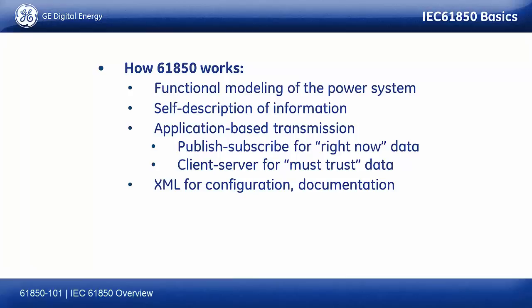What 61850 works on is functional modeling of the power system. I can break a substation down into component functions that happen in the power station. The function may be instantaneous overcurrent protection. It may be reclosing. It may be isolator switch control. It can be reporting, some function that I do. And then it works on self-description of data: when I send the data, I can put a description of the data in the message. It says, this is a phase current from the feeder 12 relay, and that I can trust it.